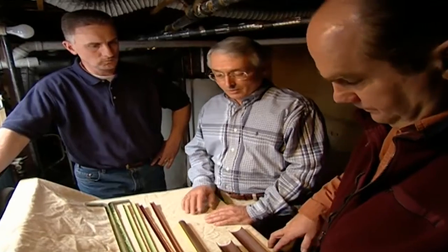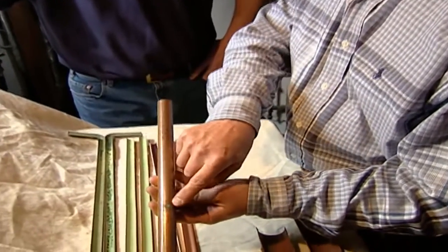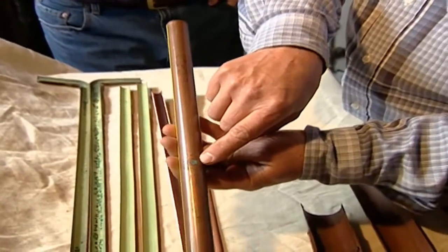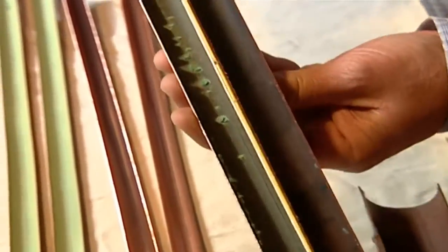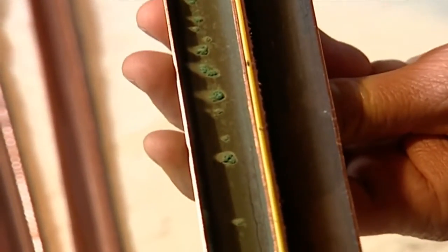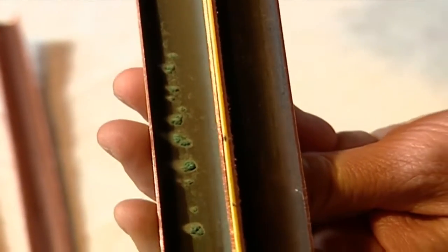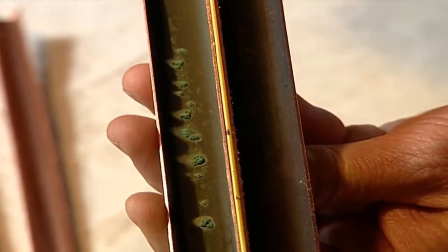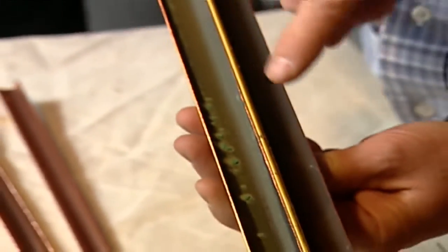Yeah, pretty much. Then we have to look at the things that can happen inside of your house. Like what? Well, one example is stagnation. Here is a piece of pipe in which we observe the corrosion product on the outside due to a leak. When we split the pipe and examine the inside, we see rows of pits. What happened in this case is the new pipe was installed and it was initially flush, but then it was allowed to remain stagnant for an extended period of time, several months. And right at the water line, inside the pipe, we have rows of pits.